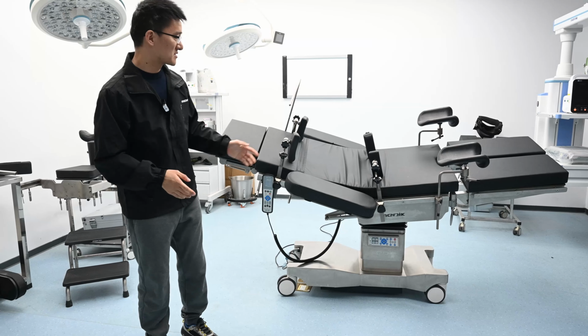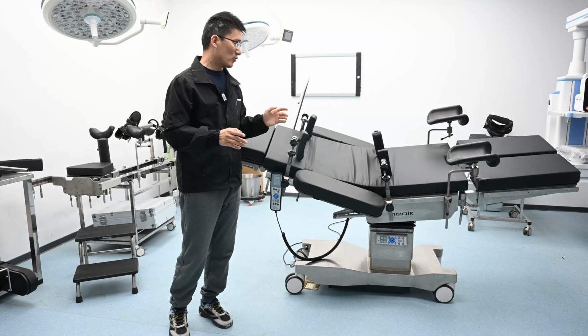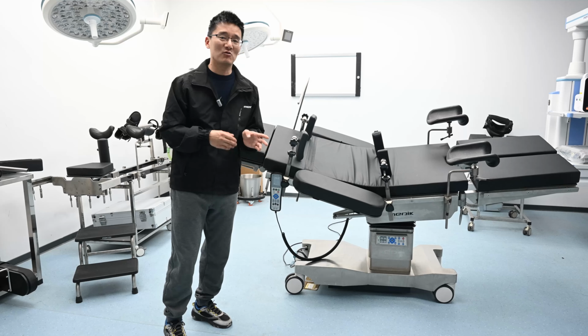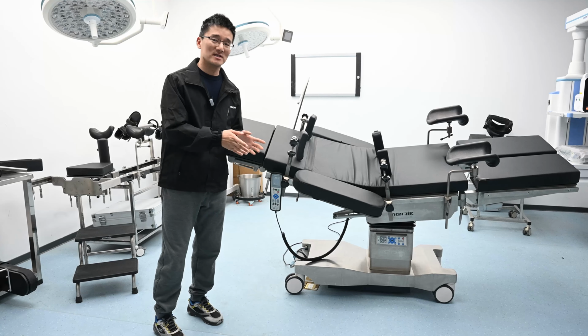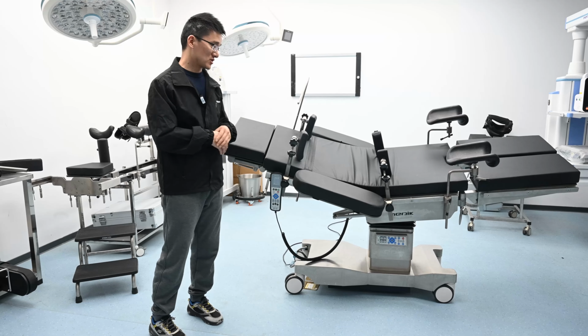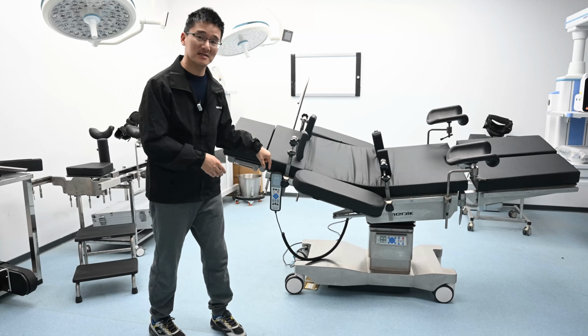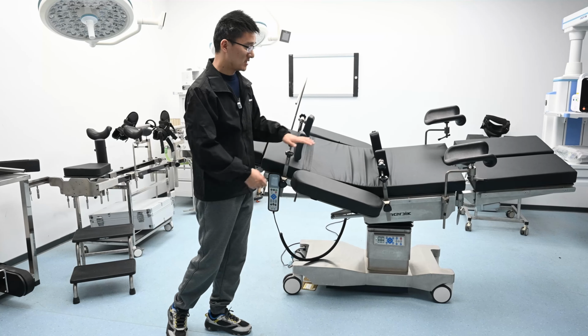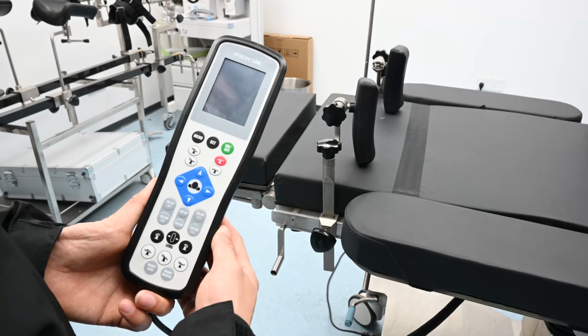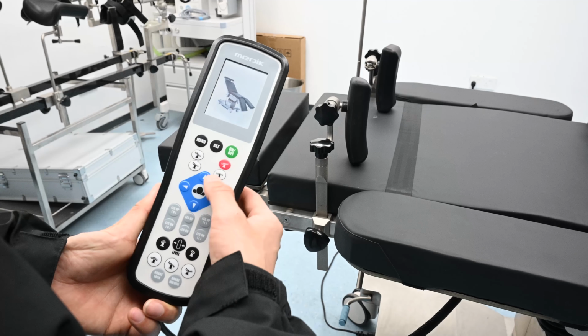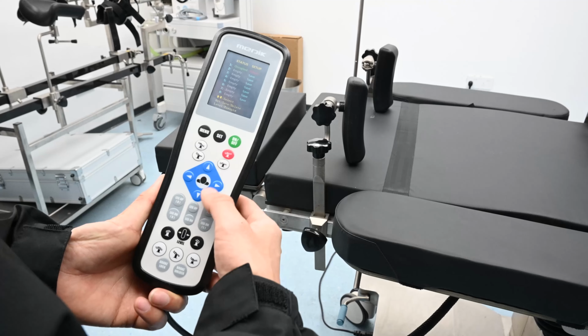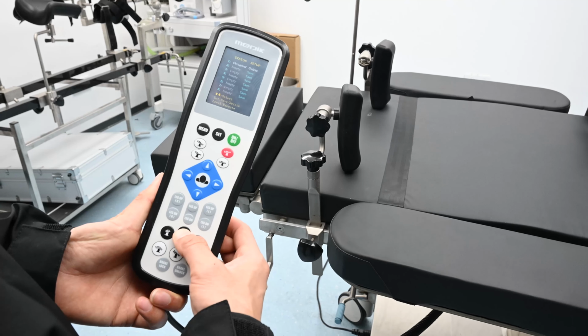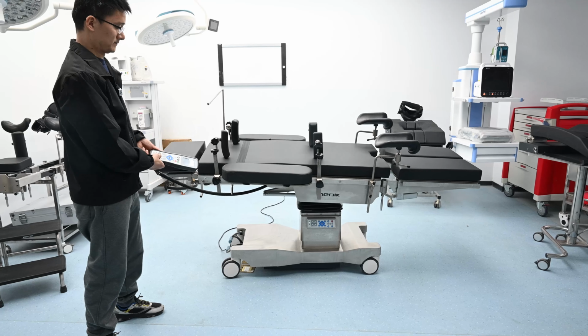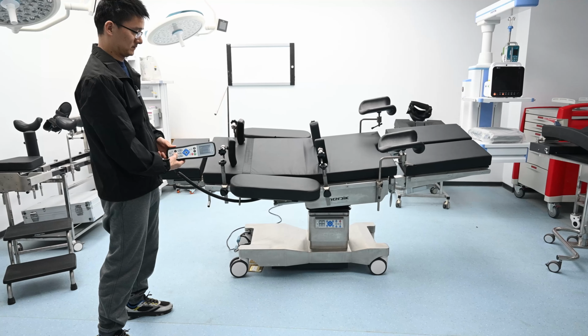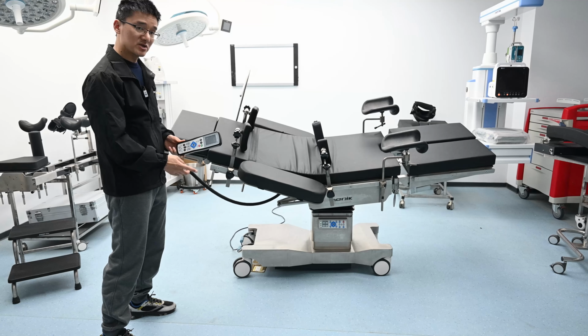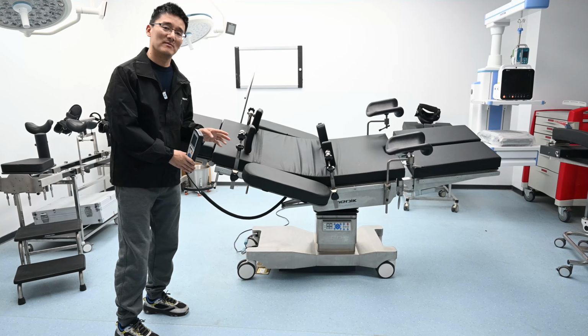A superior feature of this table is the memory function. The memory function means we can operate the table into a complicated and frequently used position, and the doctor can use it with 1 button according to their standard. For this position, we can customize it into the system. And by operating the software, we can get 1 button to make the table turn to this position. Now let's activate the saved memory positions. By option 1, now the table is turning to the preset memory position.